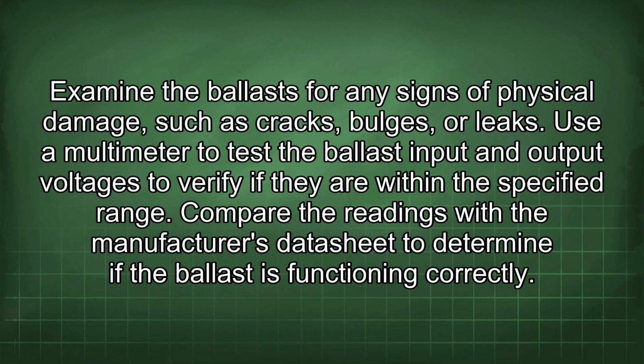Examine the ballasts for any signs of physical damage, such as cracks, bulges, or leaks. Use a multimeter to test the ballast input and output voltages to verify if they are within the specified range. Compare the readings with the manufacturer's datasheet to determine if the ballast is functioning correctly.